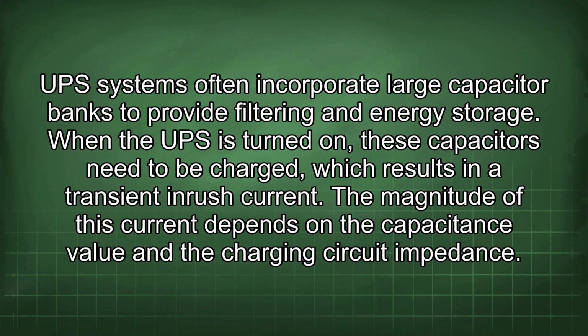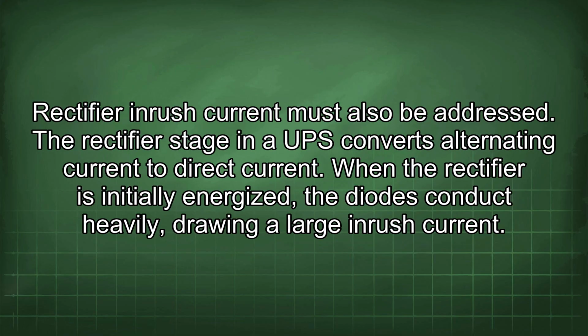UPS systems often incorporate large capacitor banks to provide filtering and energy storage. When the UPS is turned on, these capacitors need to be charged, which results in a transient inrush current. The magnitude of this current depends on the capacitance value and the charging circuit impedance. Rectifier inrush current must also be addressed.